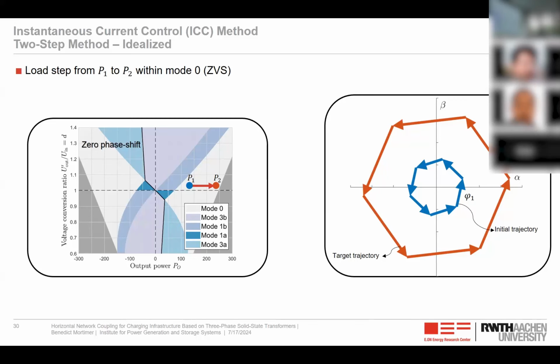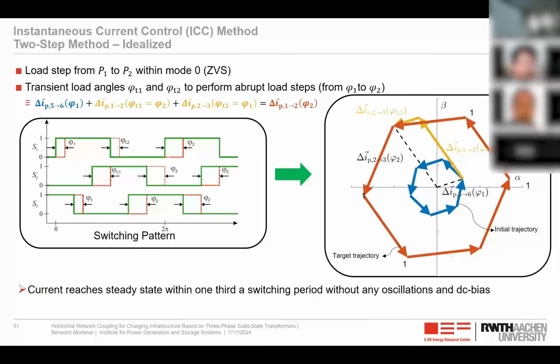So we look at the current in the alpha-beta domain. We will first have this initial trajectory, and we want to go to this red trajectory, which is the target trajectory corresponding to phi 2. And Dr. Engel proposed a method years ago for how to do this, and this is called the instantaneous current control. We use here the 2-step method, where we use 2 transient load angles to directly reach the steady state trajectory. This method proposes a first transient trajectory with the new load angle phi 2, and then a second trajectory with the old angle phi 1. Using this, we can directly reach steady state without any oscillation or DC bias of the phase currents.